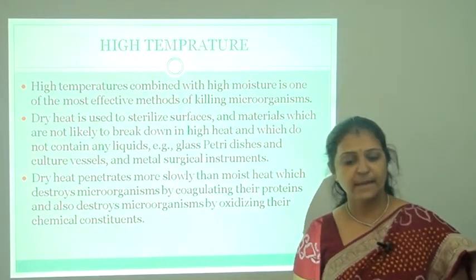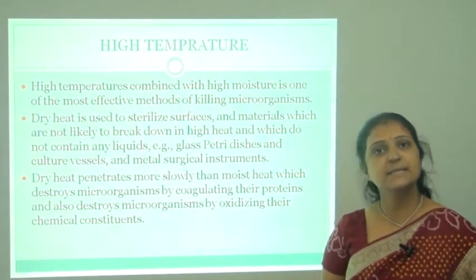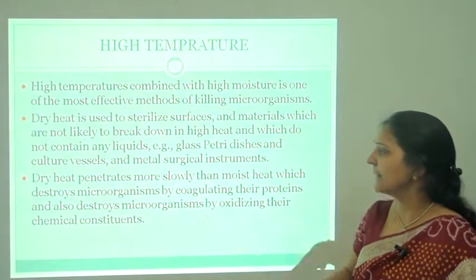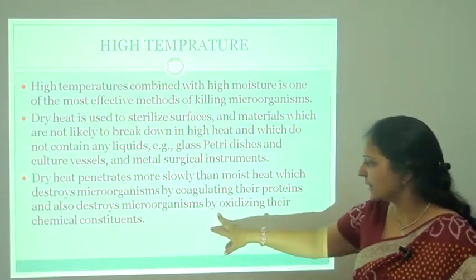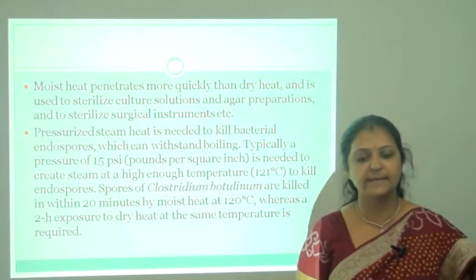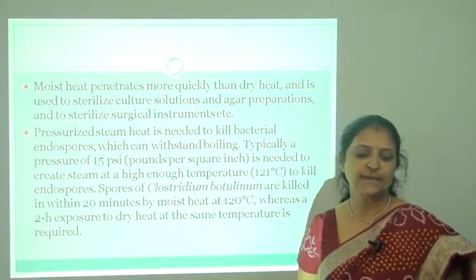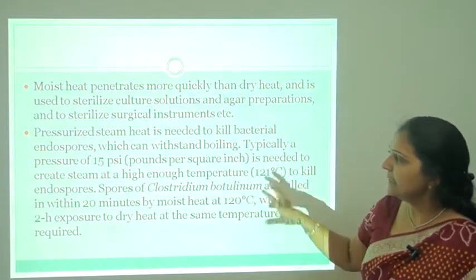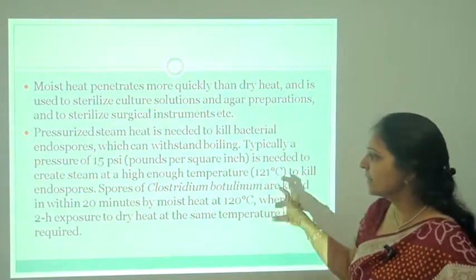Dry heat is used to sterilize surfaces and materials that do not break down under high heat and do not contain liquids — such as glassware, Petri dishes, flasks, and pipettes. Dry heat penetrates more slowly than moist heat and destroys microorganisms by oxidizing their chemical constituents. Moist heat penetrates more quickly and is used to sterilize culture solutions, agar preparations, and surgical instruments. Pressurized steam is needed to kill bacterial endospores, typically requiring 15 psi to create steam at a high enough temperature.